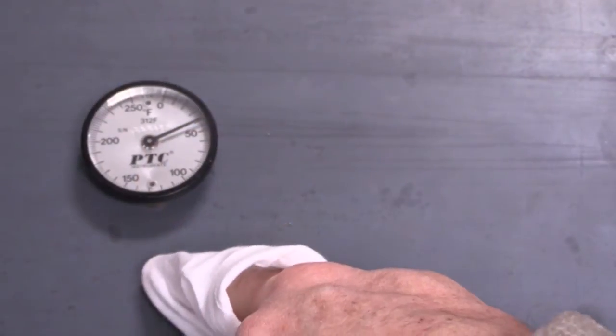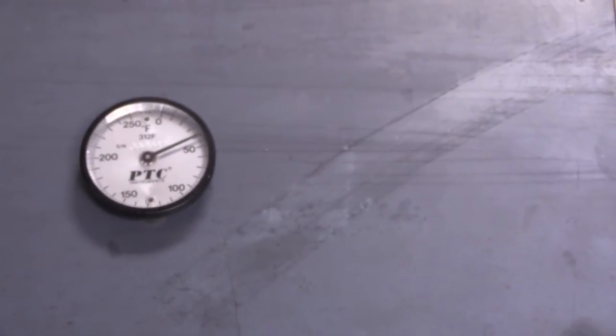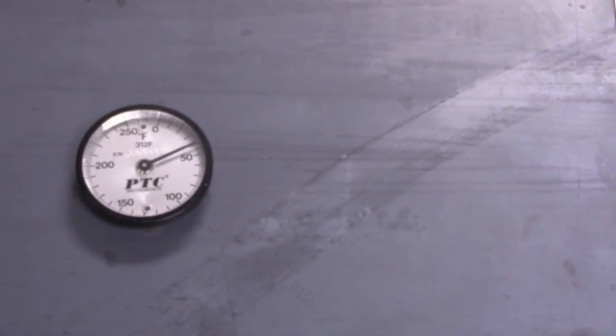In addition, many specifications and coating manufacturers require the temperature of the surface to be a minimum of 5 degrees Fahrenheit warmer than the dew point temperature to prevent moisture from condensing on the surface. While theoretically a surface temperature only slightly above the dew point temperature would preclude condensation, the 5-degree safety factor accounts for instrument inaccuracies and changing or varying conditions.